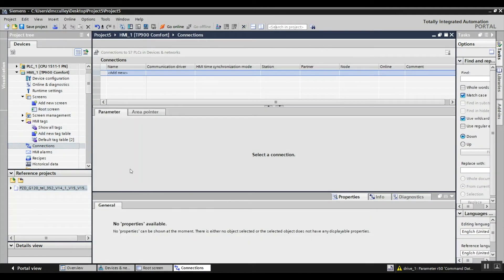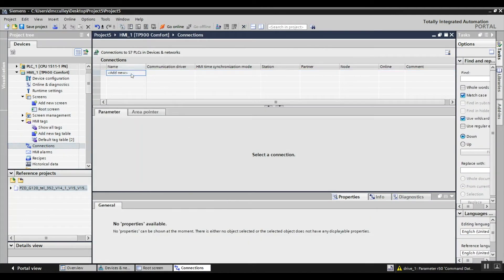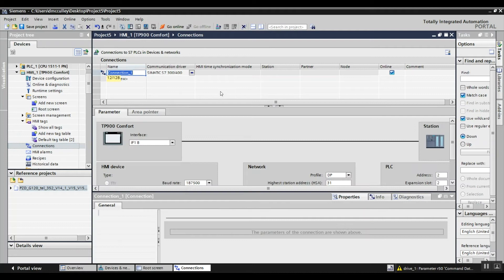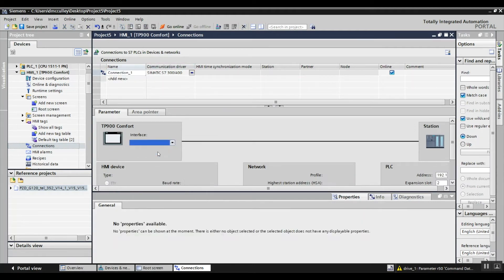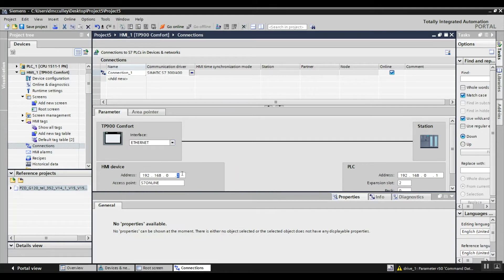Next I'm going to create a connection between the drive and HMI. The communication driver is SIMATIC S7-300/400 Ethernet. Make sure my HMI address is correct along with my drive address. If you want to do more drives, you can add more connections and just change the IP address appropriately.